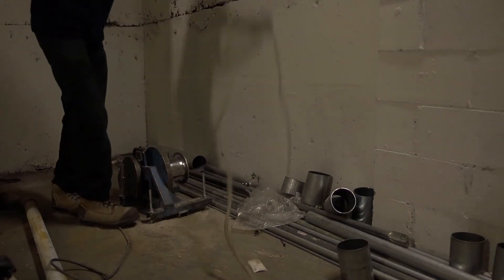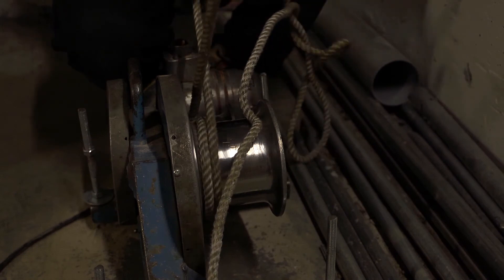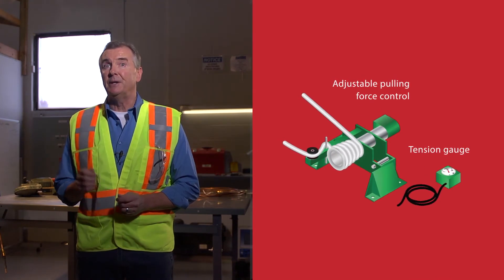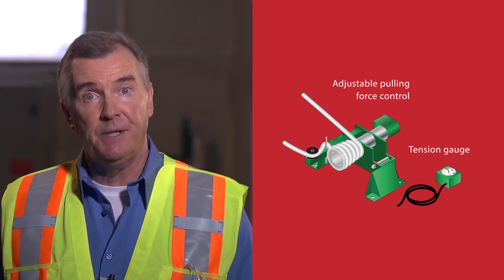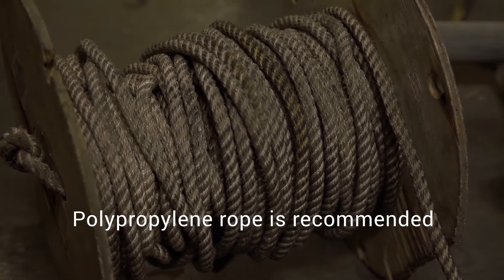Once your sheave wheels and rollers are installed, you can proceed to your tugger setup. For simpler installations, standard tuggers are commonly used, but for longer and more complex runs, we recommend the use of a tugger that has a tension gauge and adjustable pulling force control. This will limit the pulling force to safe limits for each particular cable size. Exceeding the limits can damage the cable and or factory installed splices. A polypropylene rope is recommended because it will resist stretching.